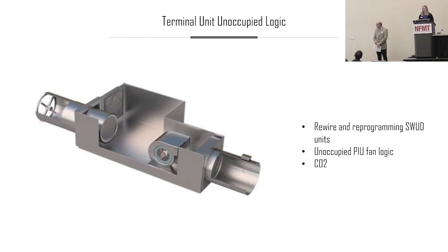So, terminal unit logic. One thing that we found at actually AdTran, our favorite customer, one of our favorites, I guess, not top favorite, but they have SWUD units, which are self-contained, water-cooled, unitary device units. So basically just a water cooling air handler. But we came in, and I forget how many they have, but it's a number of them, and they were all running at 40% VFD speed. We simply just asked the question, why are they all set to 40%? Well, the building owner said, way back when, 15 years ago, when they put this in, the units would trip at anything less than 40%, so we just set them all to a minimum of 40 and left them alone, and they've been running.